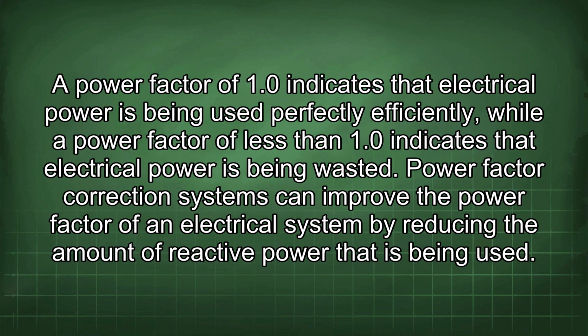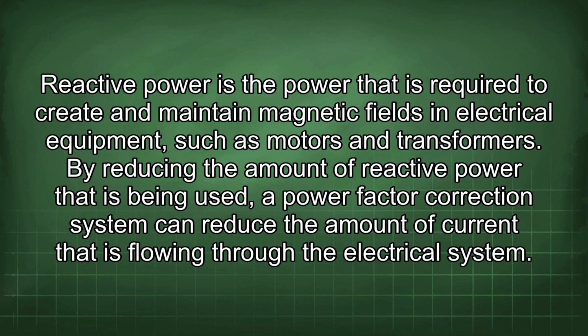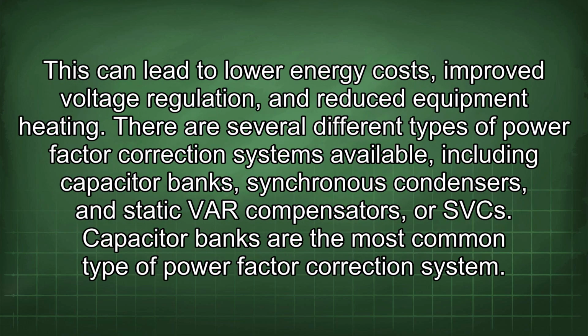Power factor correction systems can improve the power factor of an electrical system by reducing the amount of reactive power that is being used. Reactive power is the power that is required to create and maintain magnetic fields in electrical equipment, such as motors and transformers. By reducing the amount of reactive power that is being used, a power factor correction system can reduce the amount of current that is flowing through the electrical system. This can lead to lower energy costs, improved voltage regulation, and reduced equipment heating.